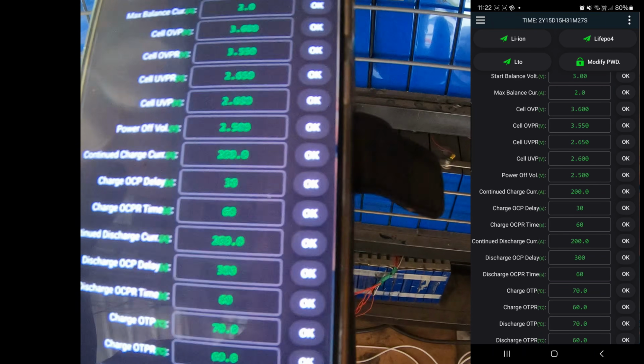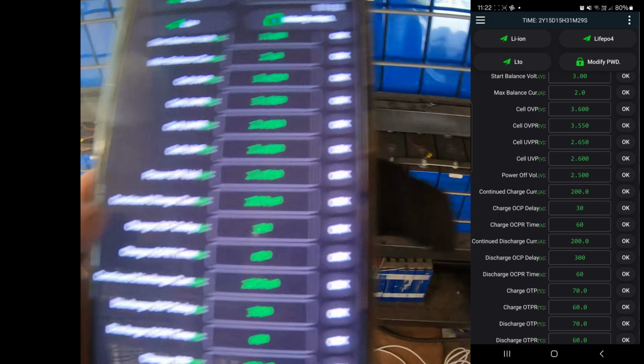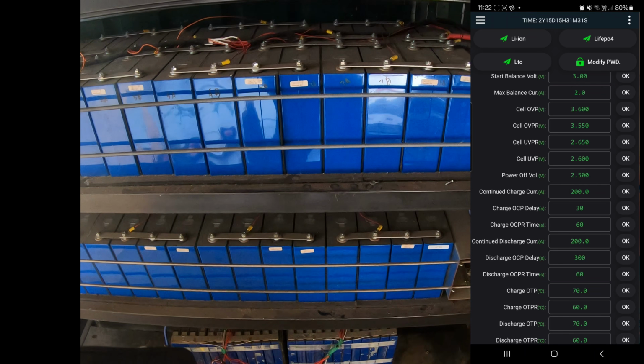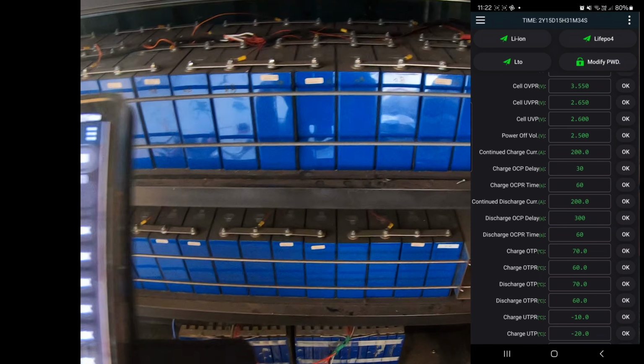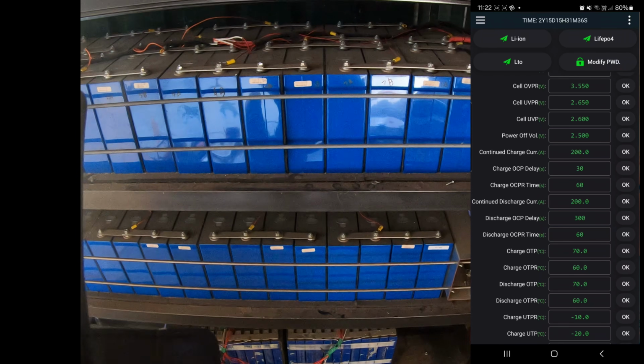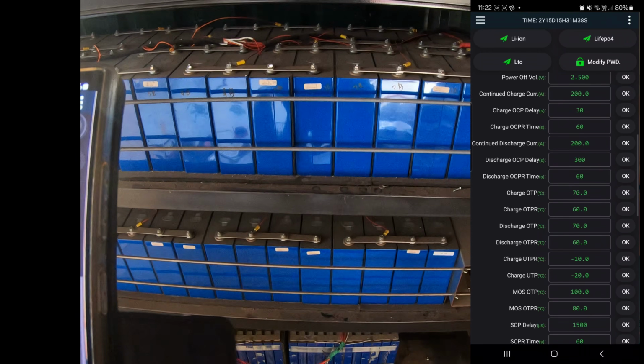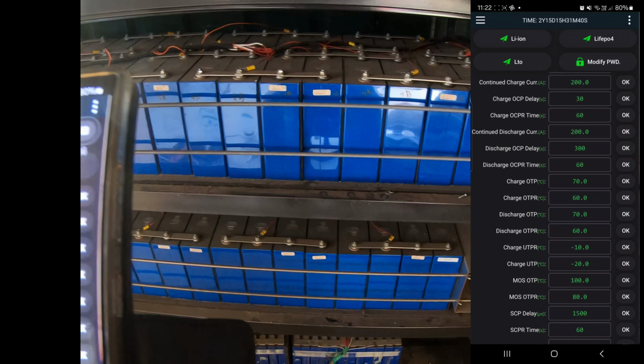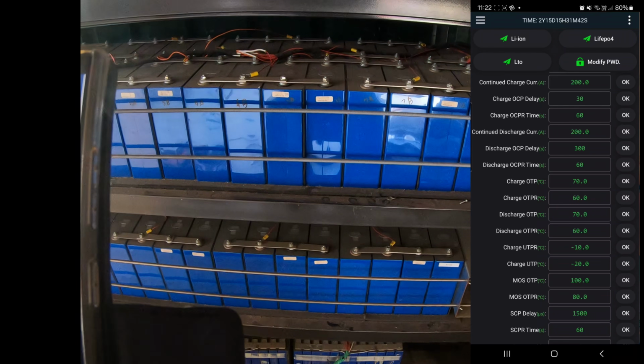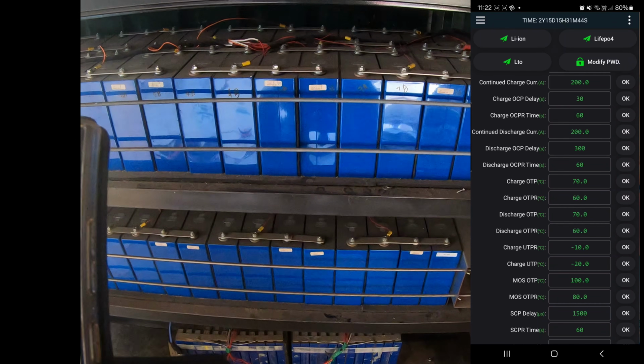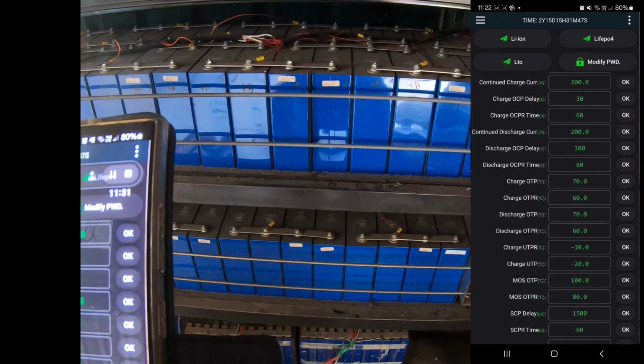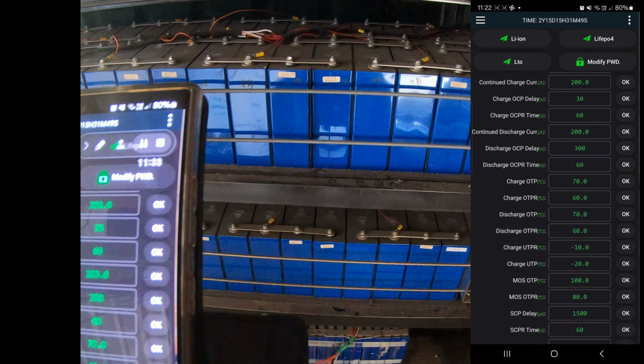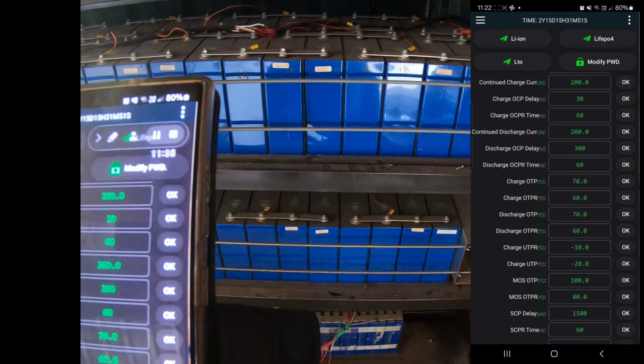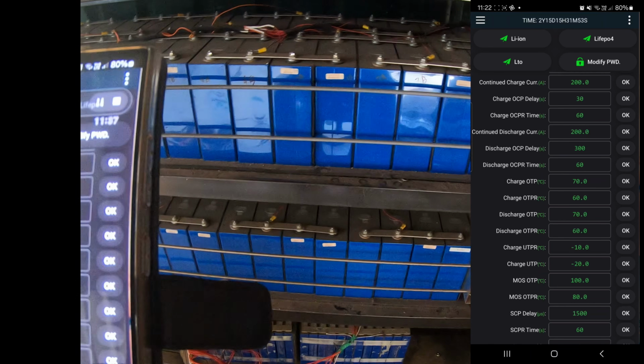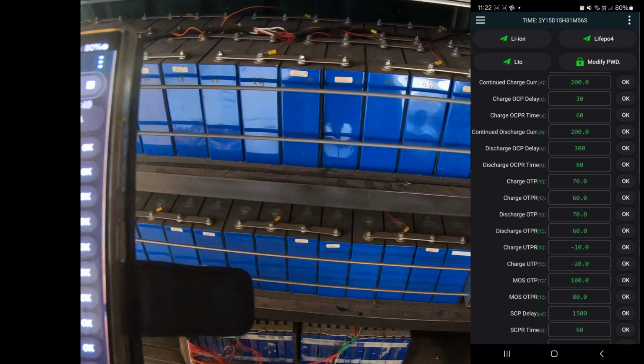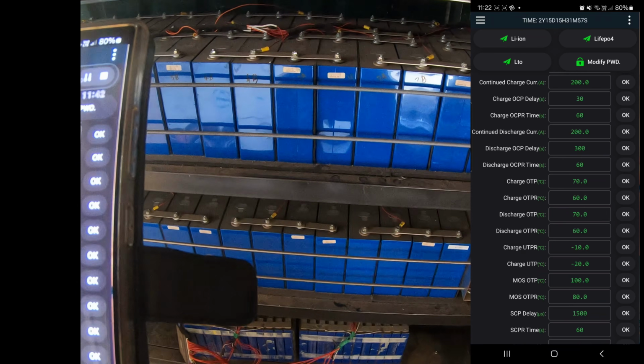Alright, what do we got here? Back to it. The continuous charge current's 200 amps. The charge over current protection delay is 30 seconds. The charge over current protection reset timer is 60 seconds. Continuous discharge current is 200. Discharge OCP delay 300. I actually don't know what that one does. The discharge over current protection delay 300 seconds. Does that mean it'll go over for 300 seconds or it cuts off for 300 seconds? I'll have to Google that. Discharge over current protection reset time is 60 seconds.